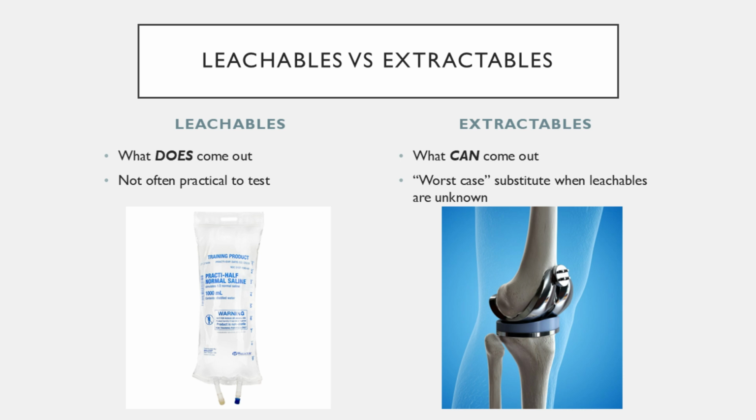You have to, under exaggerated conditions, somehow replicate that in a benchtop scenario and put in some sort of saline, a synovial fluid replicant, a physiological solution, and try and estimate what comes out of it. And you can't do it over a 10-year lifespan of however long it's going to be implanted into the patient. You have to force it.